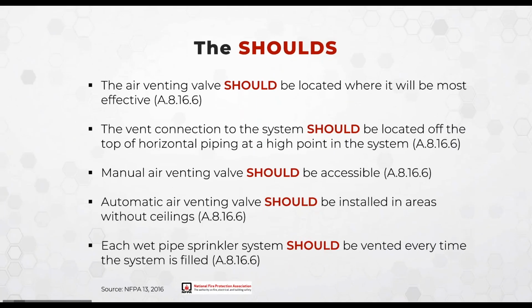There are of course some common sense shoulds. You should put it where it will be most effective. That's common sense. You should locate it off the top of a horizontal pipe. Why? Because if you feed it from the side of a pipe, or in the worst case, from an arm-under arrangement, feeding it from the bottom of the pipe, then you are impairing the air vent from having access to the most accumulated air to get it out. So you always want to make sure they are fed from the top of the pipe.